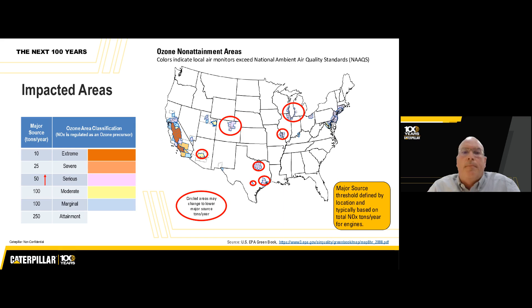As you look to expand your site's power capacity, staying compliant with emission regulations becomes a critical part of the planning process. This is where aftertreatment solutions come in. Tier 2 emergency use only generators can meet Tier 4 emission levels if equipped with the proper aftertreatment system. This means you can add more gensets and increase your site's capacity without exceeding regulatory limits.